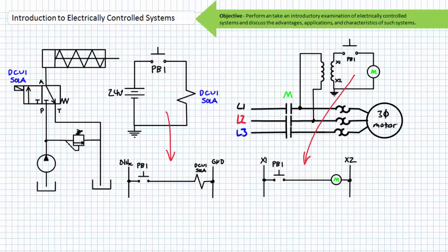A ladder logic diagram basically flattens out a series path into a single line, and it makes readily apparent that in order to complete a conductive path from the hot or high side through solenoid A to the low or neutral side, one must close push button 1. A ladder logic diagram for the electrically controlled motor system is almost identical. Again, the ladder logic diagram flattens out the series path of the traditional schematic into a single line, and it makes readily apparent that in order to complete a conductive path from the hot or high left side through the coil M to the low or neutral side X2, one must close push button 1.